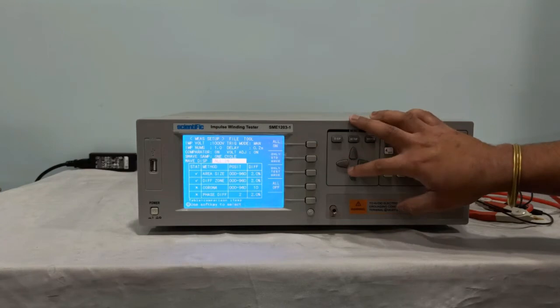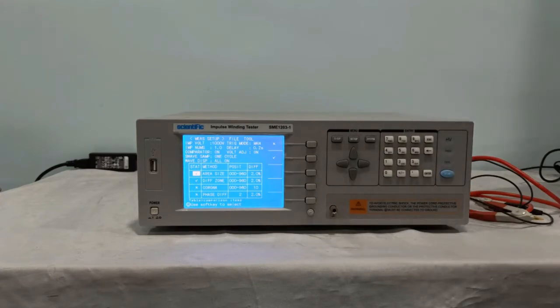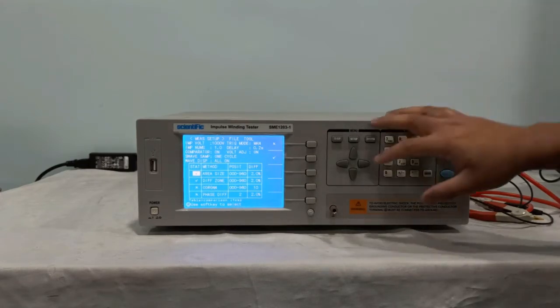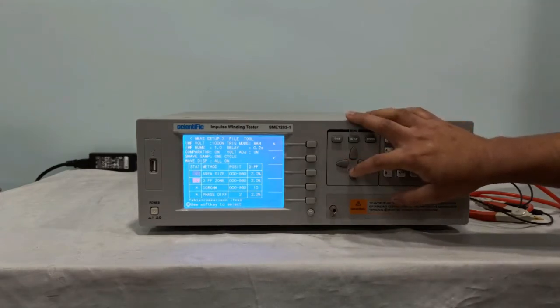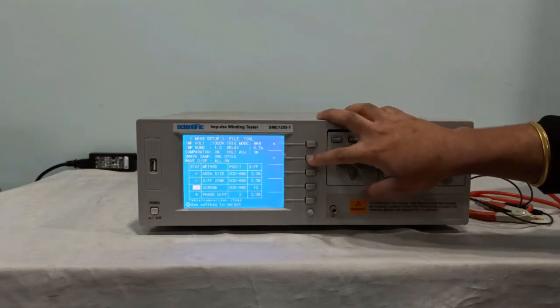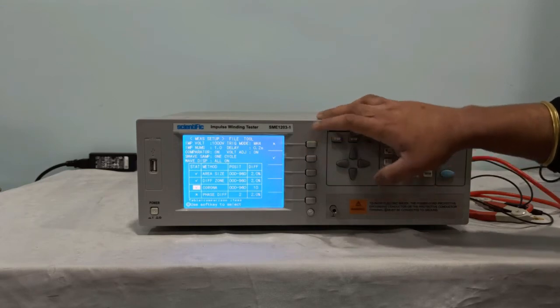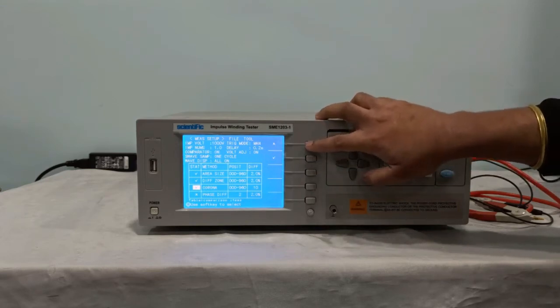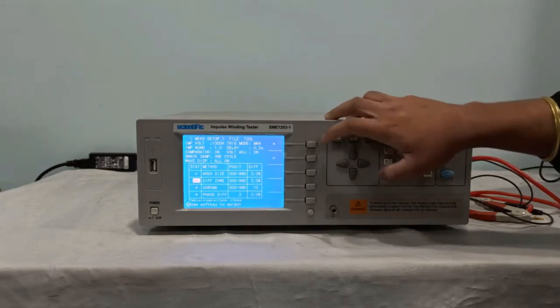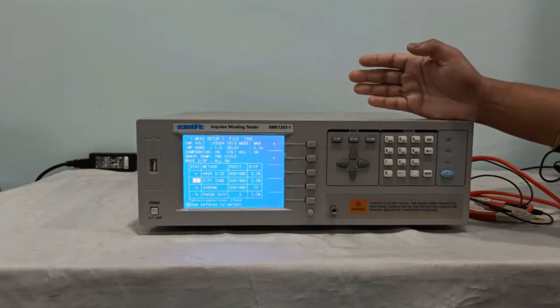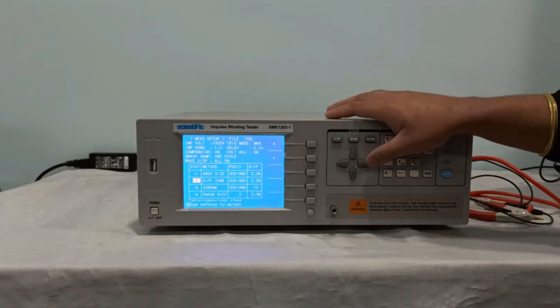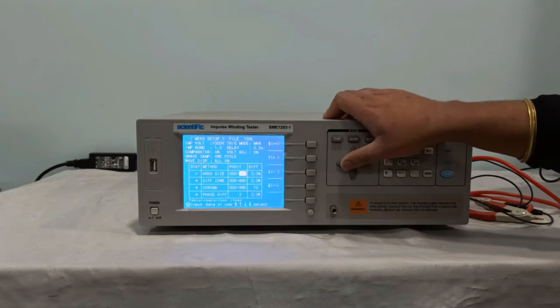So these are all 4 comparison methods that you can use according to your application. Right now what we have selected is area size and differential zone. If you want to enable corona, you can enable it like this, or if you want to disable any of the comparison methods, you can uncheck this. So this is how you can set the comparison methods.